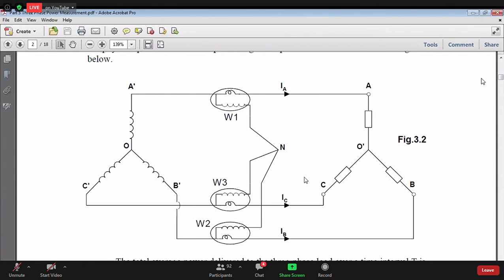Now, sir, you have raised a point. The three lines from the three wattmeters W1, W2, W3 at the N point that you said to twist, does twisting mean joining the three lines? Exactly. Twisting means take a plier, if you have seen a plier, take the three wires and twist them. That's it, nothing more, just joining them. Just an electrical connection, so that they are not electrically disconnected. That's all. There is no other requirement.